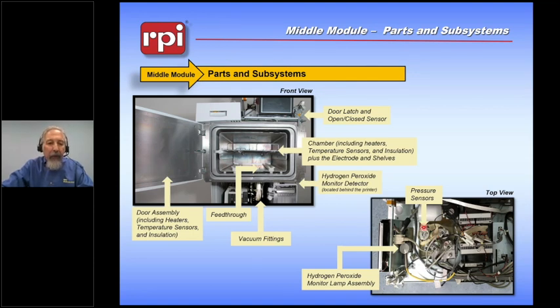Also within the door frame, we have heaters to prevent the hydrogen peroxide from condensing on the inside of the door. We have a monitoring system for the hydrogen peroxide, which starts at the top of the chamber with a UV lamp that sends light through three separate lenses, one that's mounted here at the top of the chamber, one that's mounted here at the bottom of the chamber, and one that's mounted right above something called the hydrogen peroxide monitoring detector, which is screwed into the bottom behind the printer.